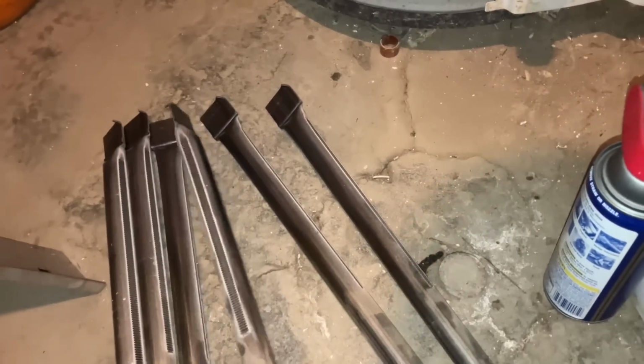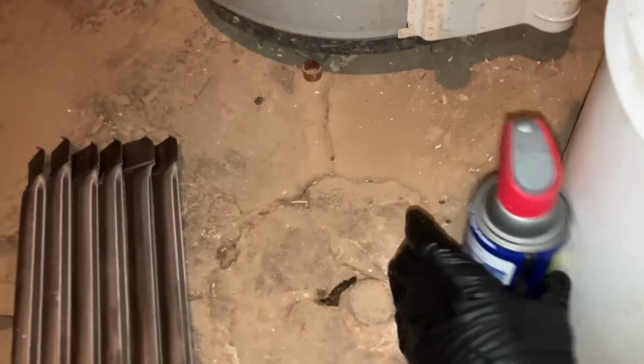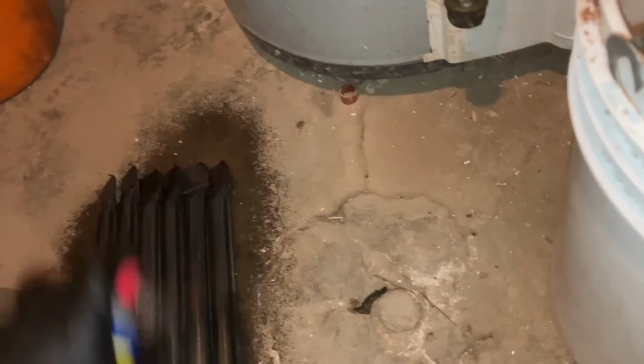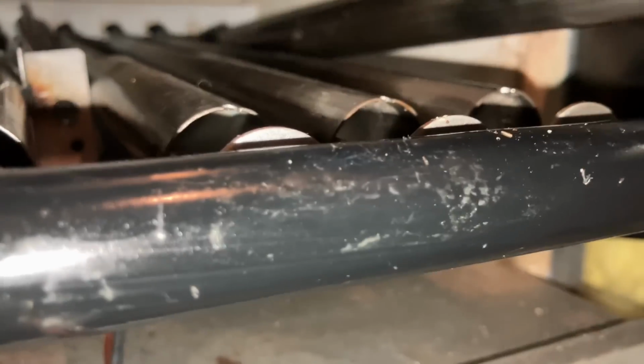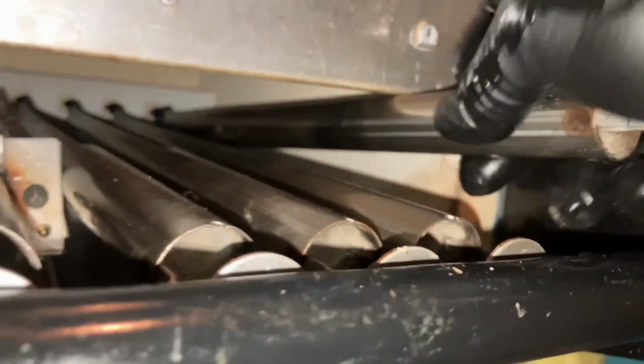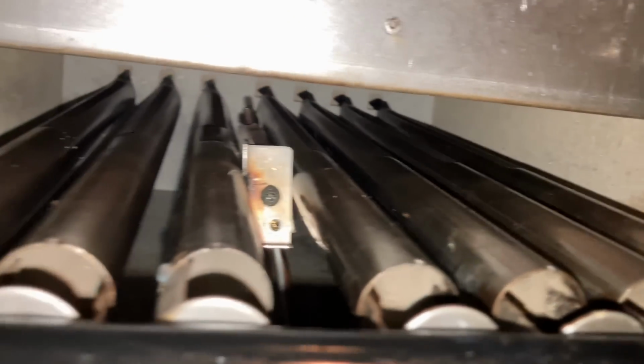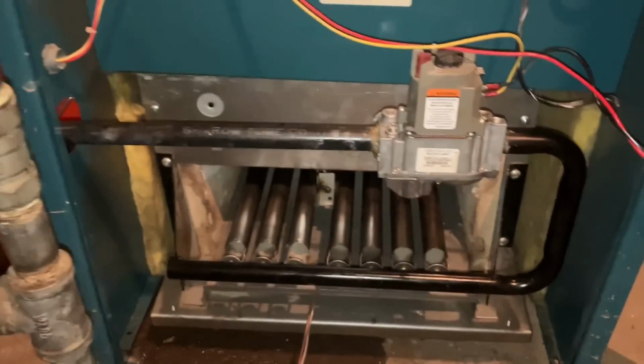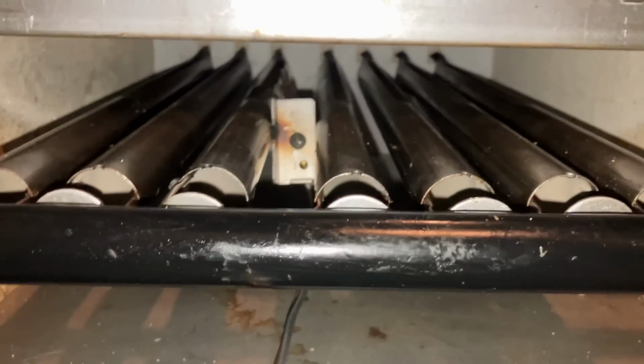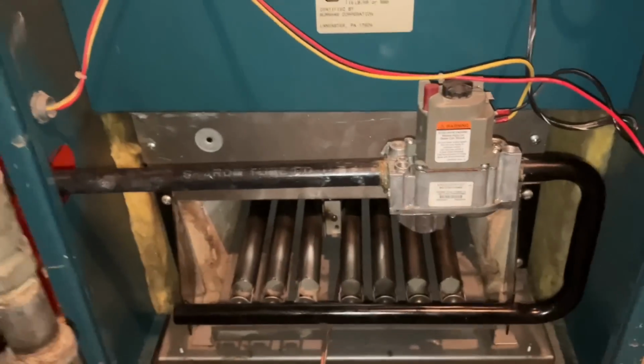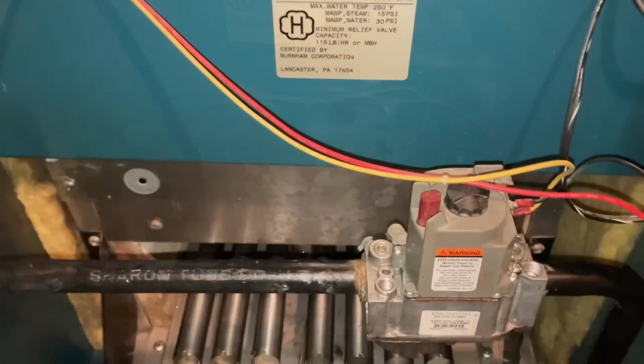Very nice. Now I'm going to spray down all of my burners with some WD-40. Beautiful. Let that penetrate for a hot minute, and then wipe them all down. All right. The hardest part, I tell you, with Burnham boilers, the Steam Series 2, is getting those burners back in. It's the hardest part of working with Burnham boilers. So they're all back in there. Look at that, that looks very, very nice. Let's reconnect the pilot and the thermocouple, and then we'll relight the standing pilot.